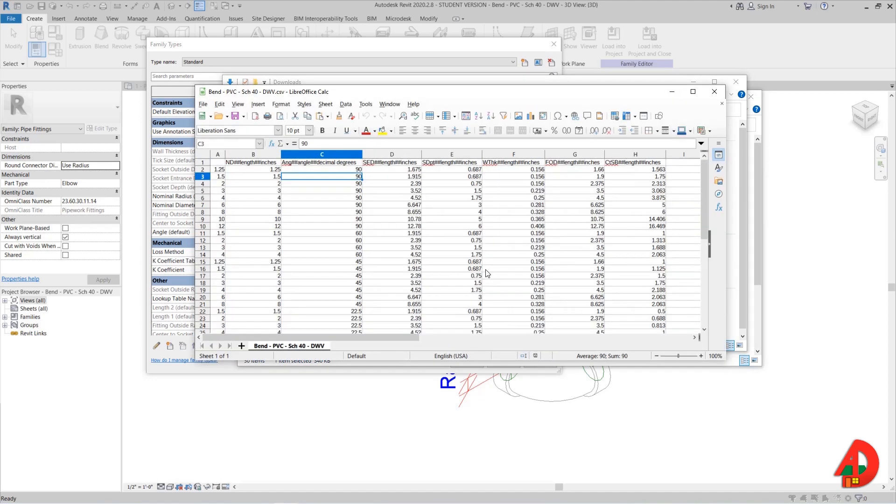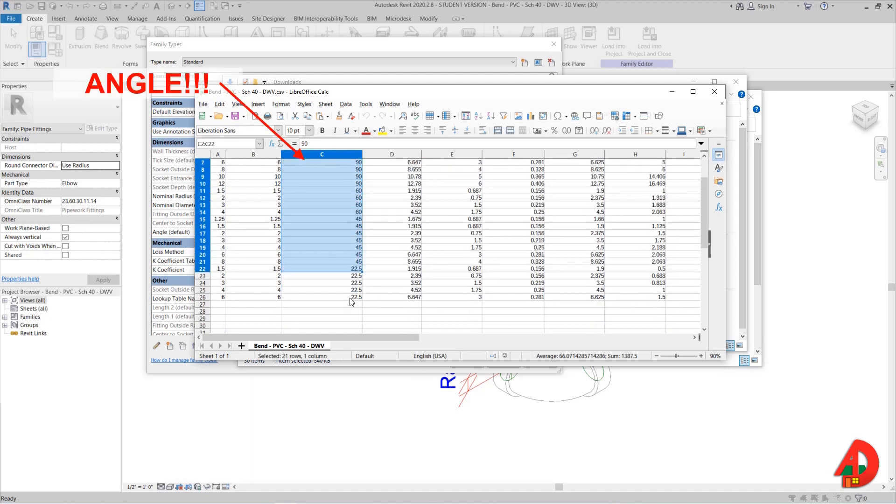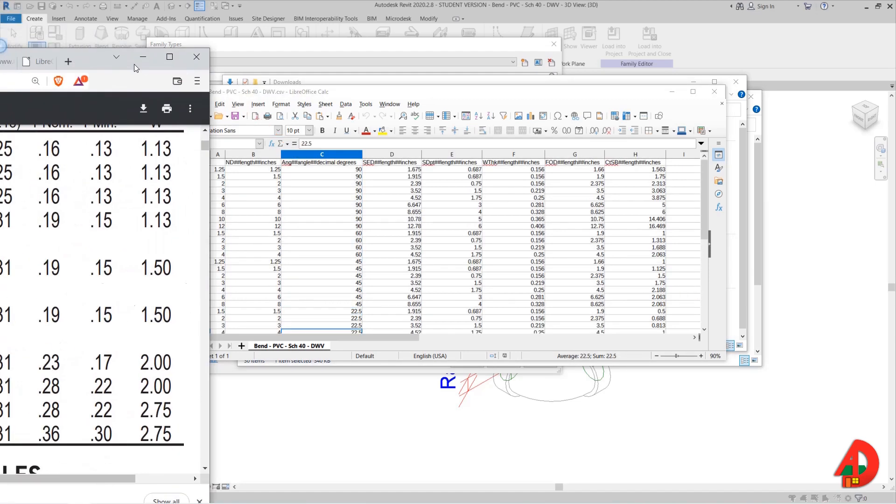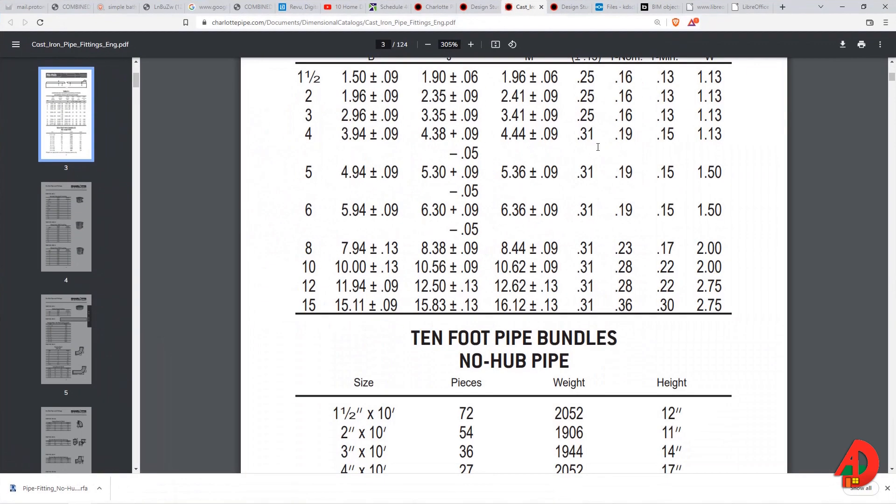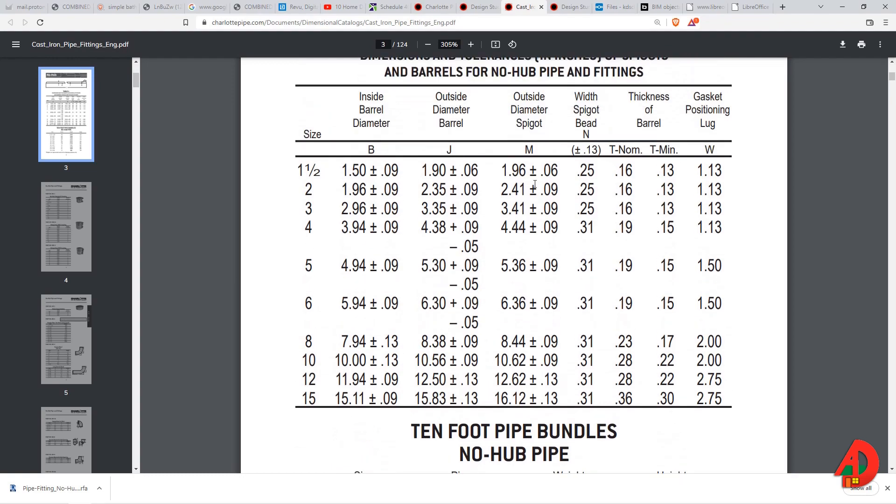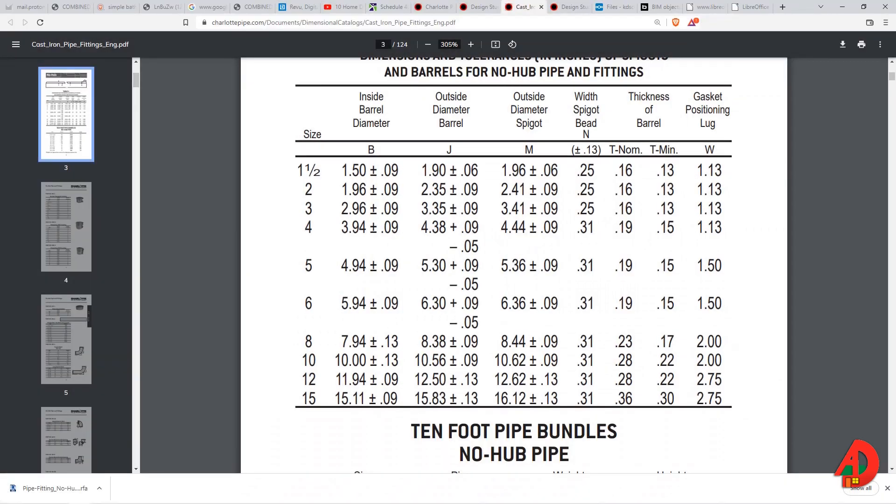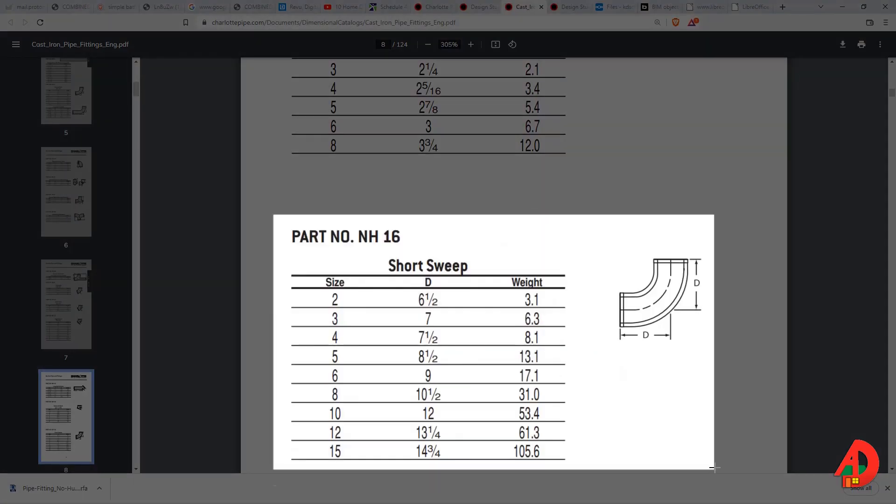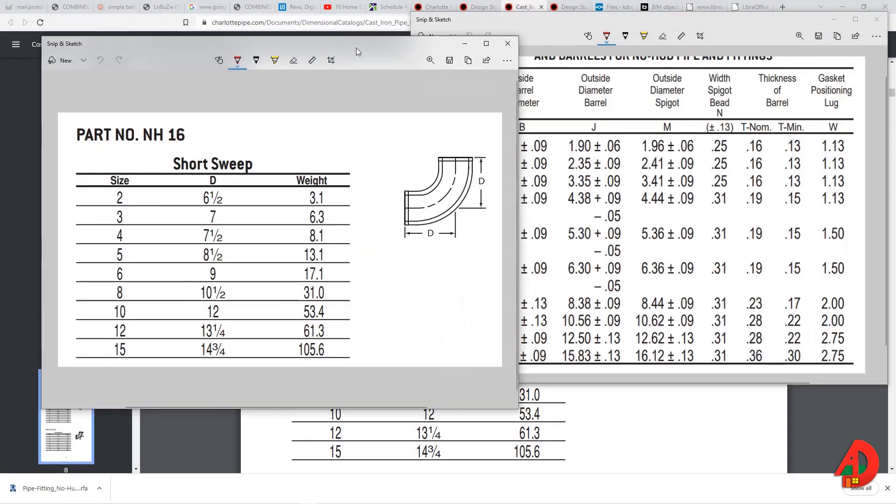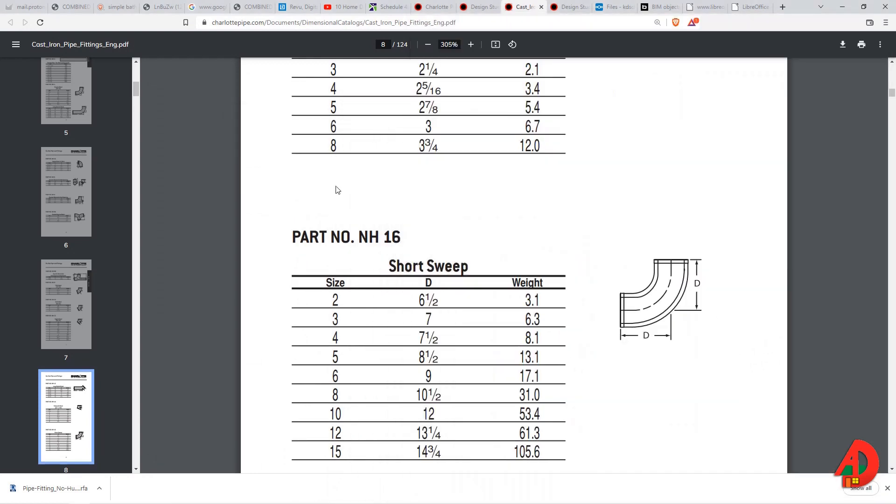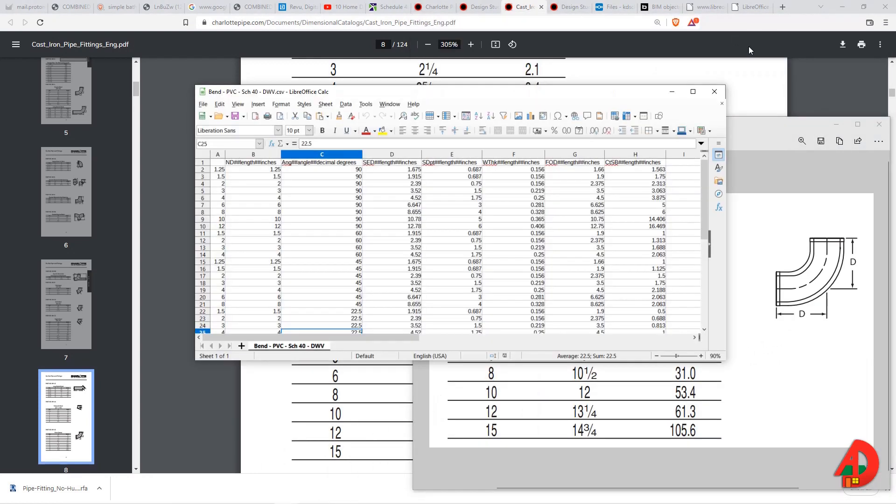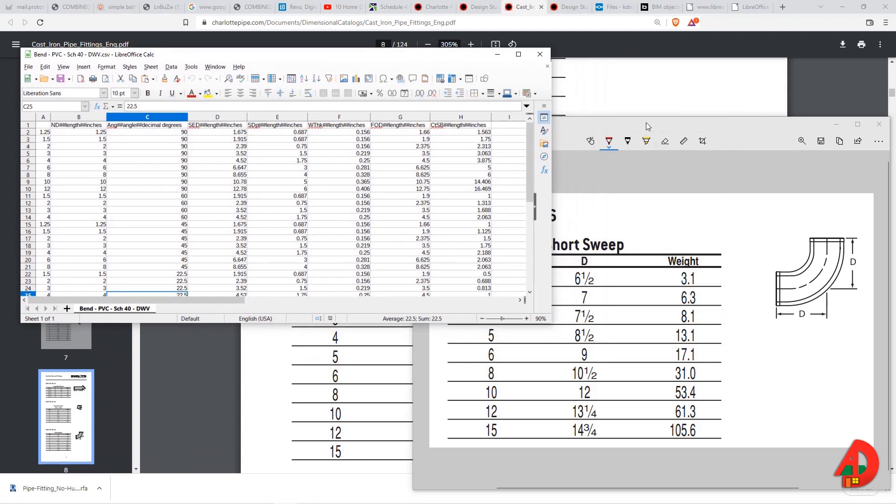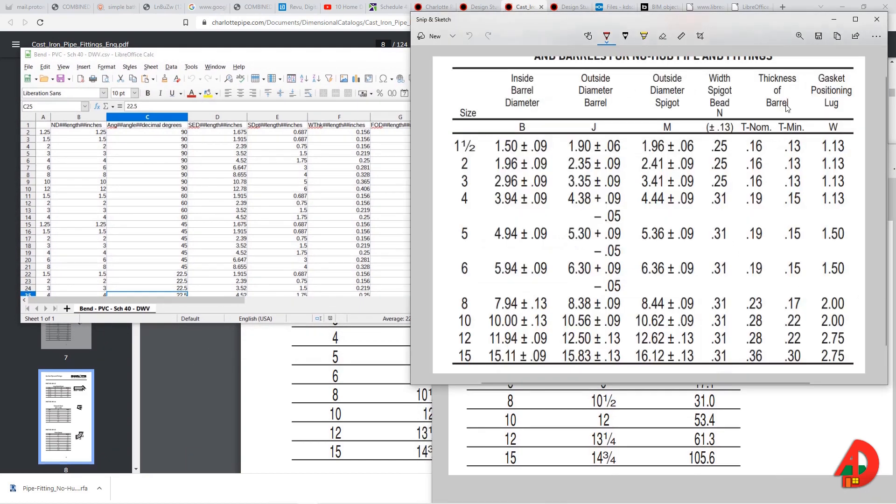So this is a similar lookup table but it has a specially designated column for angles, so I can control the dimensions of the fitting not only by diameter size but also by angle. Now I will fast forward where I take some snapshots from the cast iron no-hub PDF provided from the manufacturer website. What I need is the dimensions of the fittings and the dimensions of the pipe. Using Alt and Tab to switch between windows will be very helpful in this process.